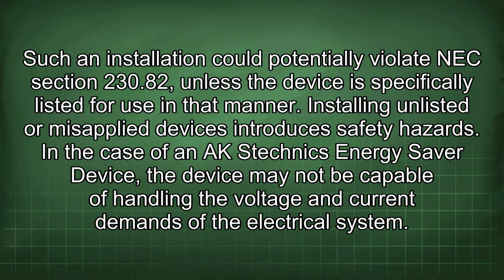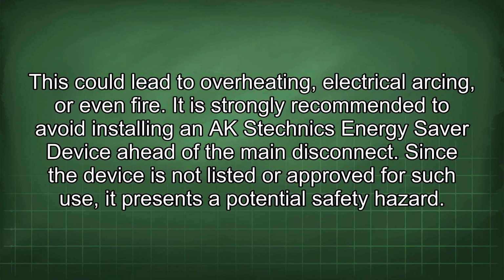In the case of an AK Stechnics Energy Saver device, the device may not be capable of handling the voltage and current demands of the electrical system. This could lead to overheating, electrical arcing, or even fire. It is strongly recommended to avoid installing an AK Stechnics Energy Saver device ahead of the main disconnect. Since the device is not listed or approved for such use, it presents a potential safety hazard.